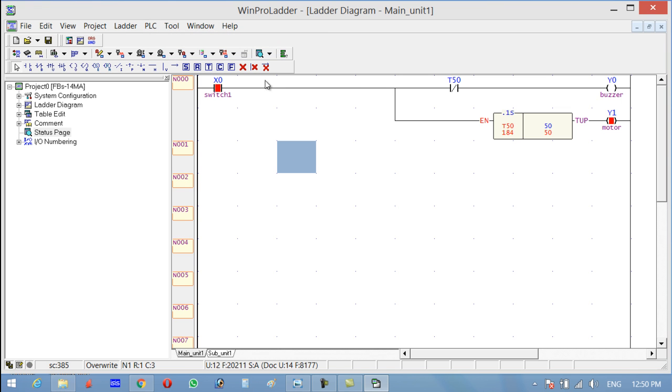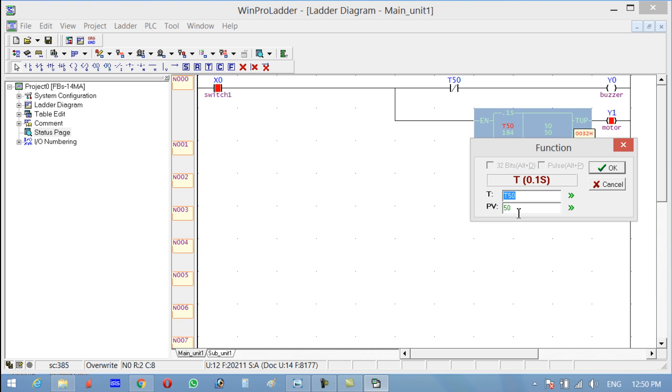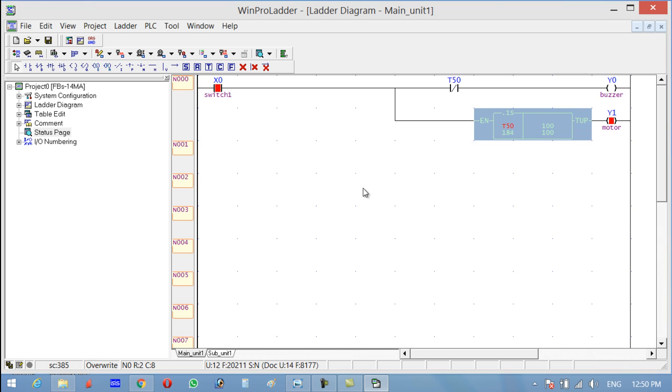This is a very small program and it can be used with all types of crusher machines and compactors. And the amount of delay can be changed from here. For example, this time I want to make it work 10 seconds, so I will write 100. 100 multiplied by 0.1, that is 10 seconds. And now you'll see it will wait for 10 seconds.